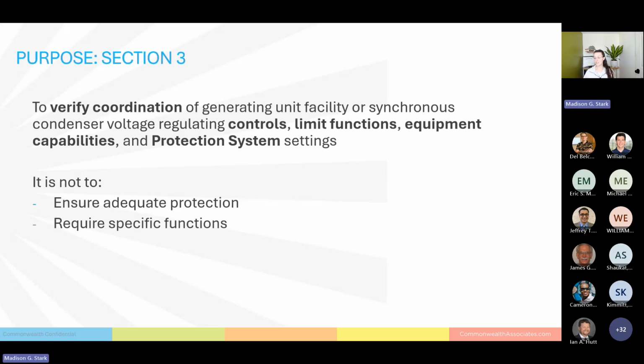To kick it off, what is the purpose of PRC 19? What does it do for the bulk electrical system? The intention of PRC 19 is to verify coordination of the generating unit or synchronous condenser, their regulating controls, limit functions, equipment capabilities, and then their protection system. What it does not do is ensure adequate system protection or require any specific coordination or equipment functions. So just because you're PRC 19 compliant doesn't mean your system is necessarily adequately protected. What it does is make sure that all of the elements you have in play are properly coordinated for the system.